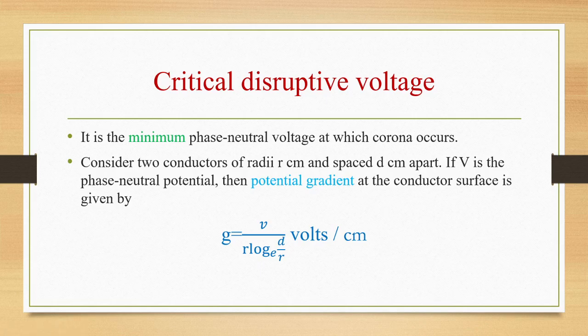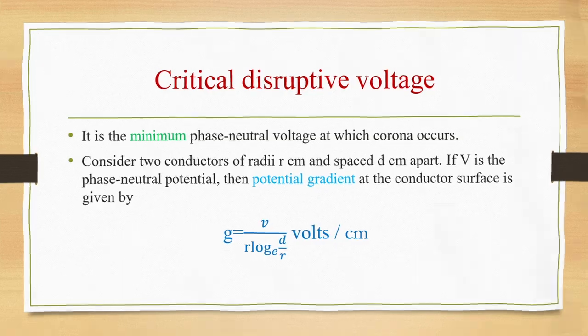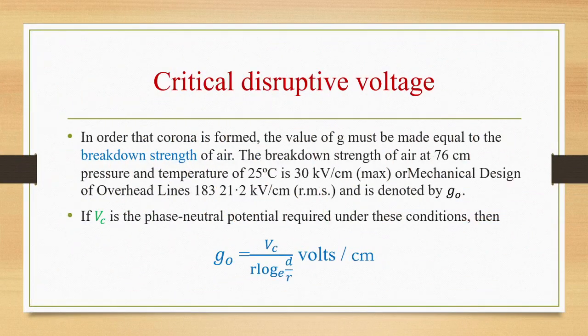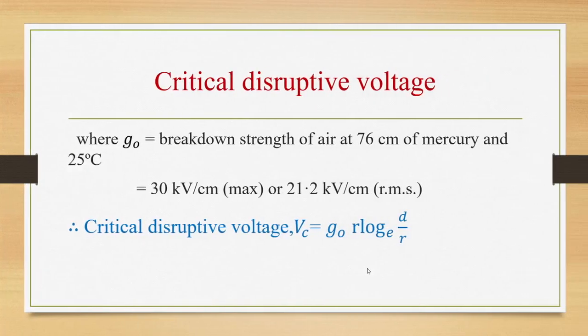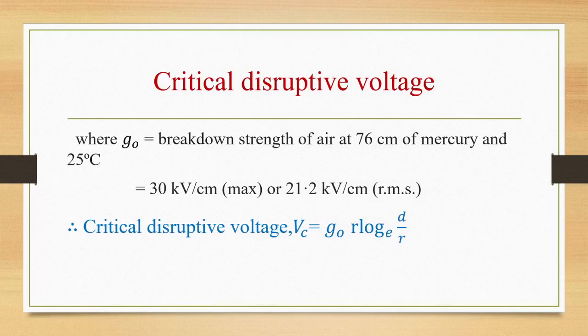In order that corona is formed, the value of g must be made equal to the breakdown strength of the air. The breakdown strength of air at 76 centimeter pressure and temperature of 25 degrees centigrade is 30 kilovolt per centimeter maximum or 21.2 kilovolt per centimeter RMS value, and it is denoted as g naught. If Vc is the phase neutral potential required under this condition, then g naught is given as Vc by r log d by r base e volts per centimeter. Therefore, critical disruptive voltage Vc is given as g naught r log d by r base e.